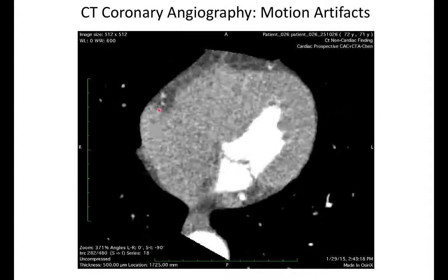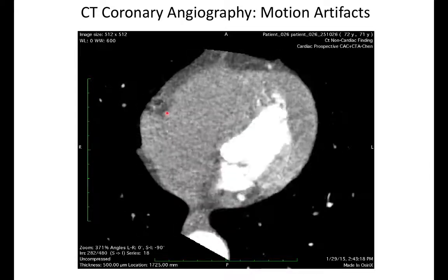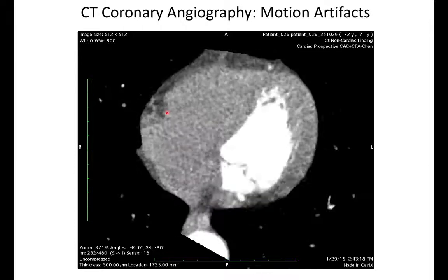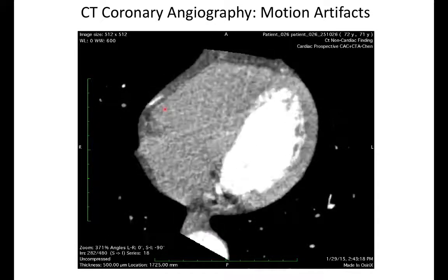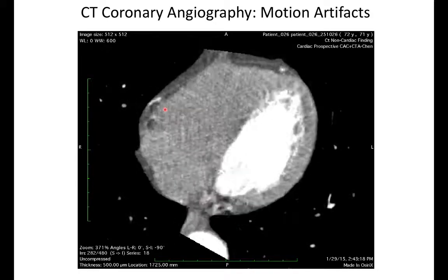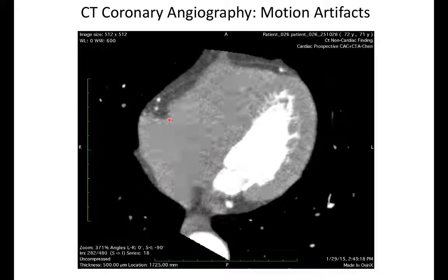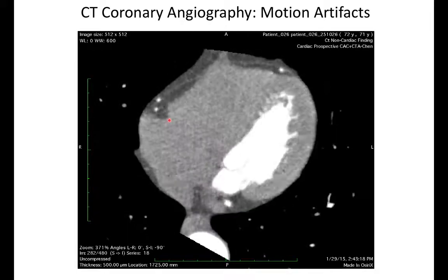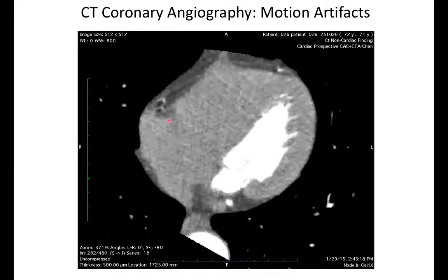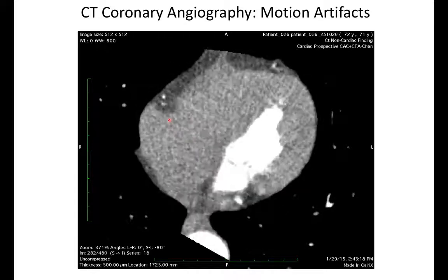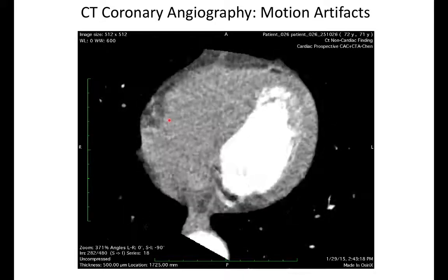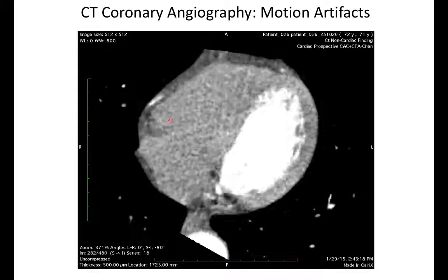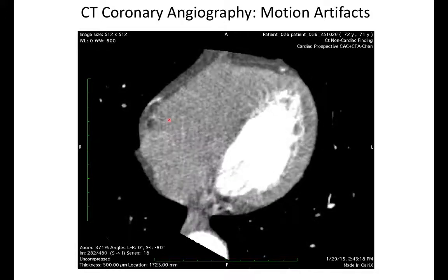And you can see the characteristic motion artifacts, right? So when the heart's stationary and we can image it while it's still in the same configuration, we get really nice dots that are cross-sections of those vessels. And then when it's in motion, they turn into pretty crazy looking pictures, right? Some of them look like swirls, others are just streaks across, and that all depends on what the motion is with respect to the gantry position, as that motion is occurring.